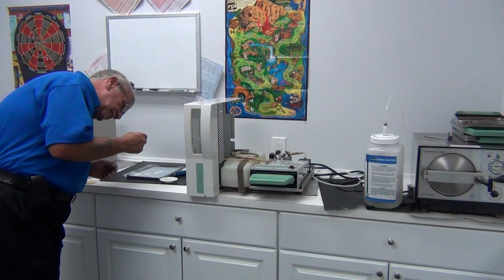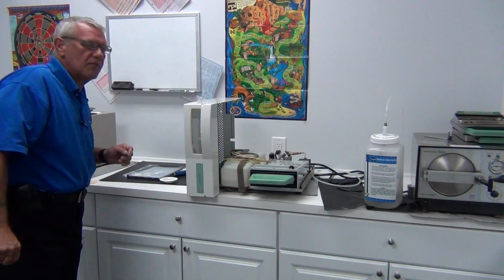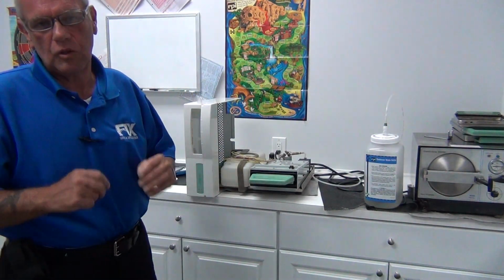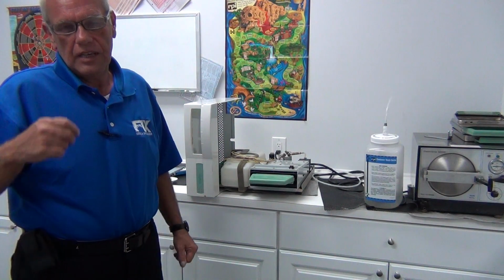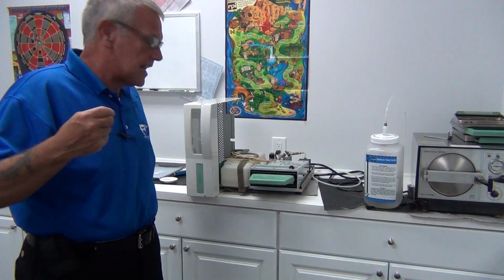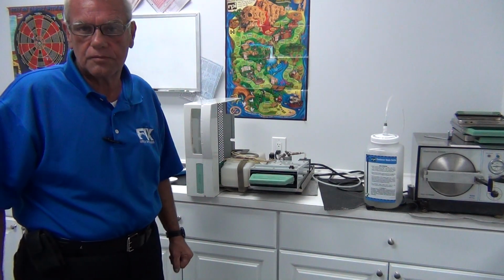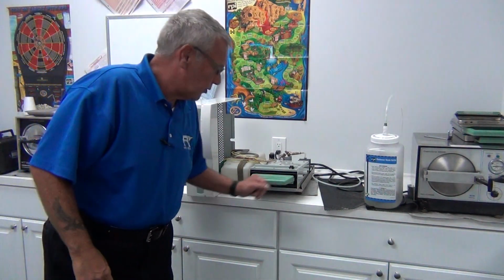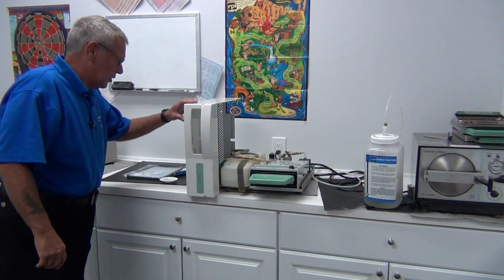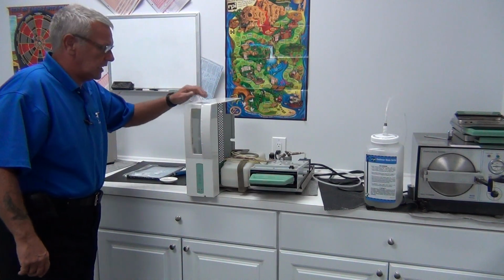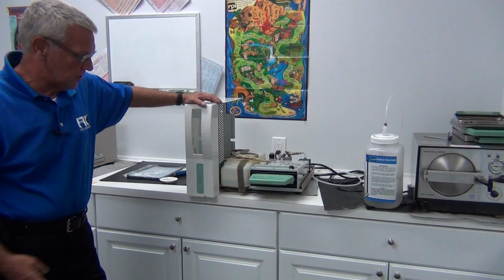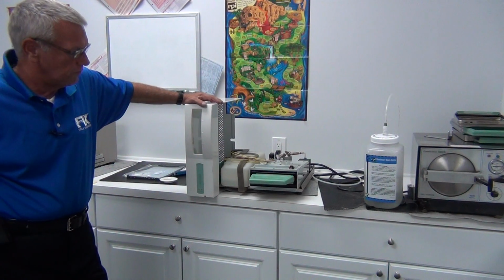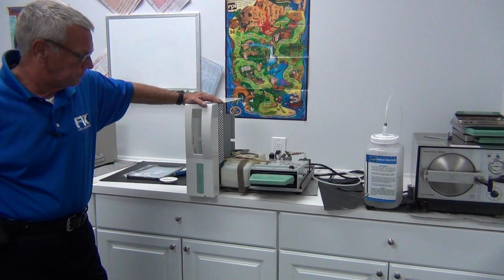We're already into the sterilization cycle and we have 3 minutes and 25 seconds to go. That is phenomenal in a sterilizer. In 3 minutes and 10 seconds now, we'll have sterile instruments. Not a problem. Now, if we want to shortcut the process, we will hit off on the keypad. You hear us vent. We're venting into the condenser bottle.